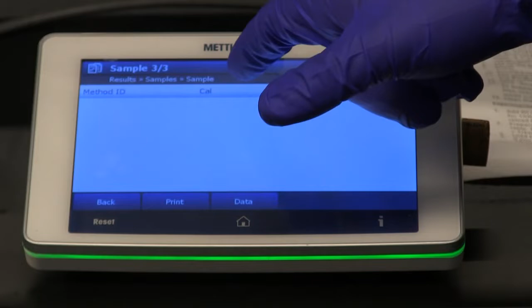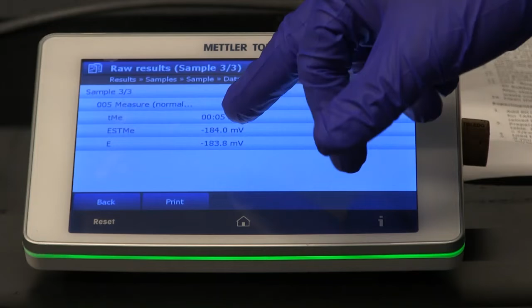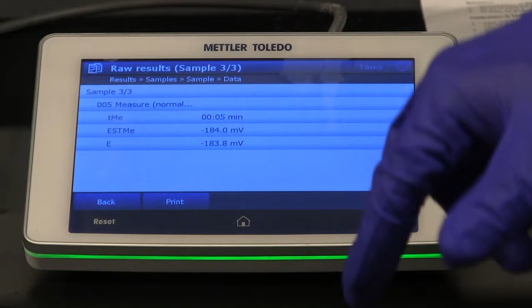And for the third one, is okay because it's around minus 183. It should be minus 177. So that value is fine. So the third buffer is okay, but the first and second one need to be changed. So we have to do that and we do the calibration.